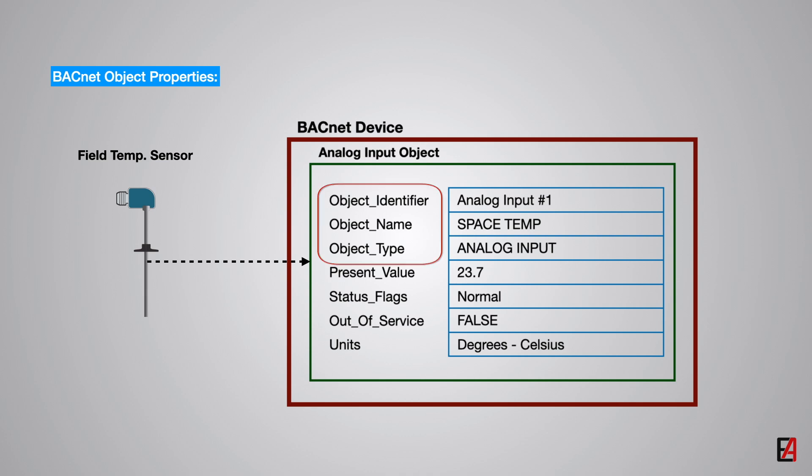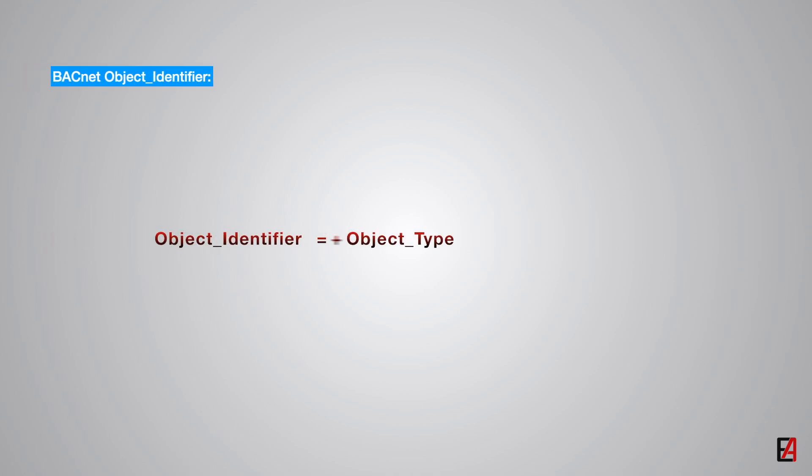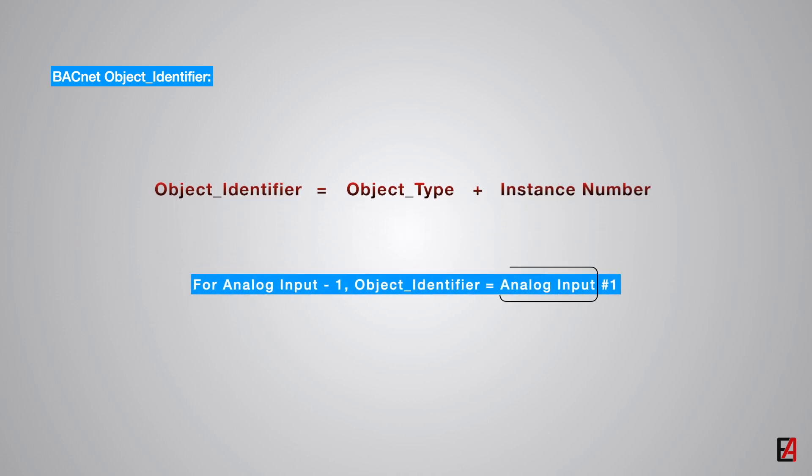The first three properties object identifier, object name and object type must be present in every object in a BACnet device. One of the most important properties is the object identifier. It is a 32-bit code that identifies the types of object and its instance number which together uniquely identify the object within the BACnet device.